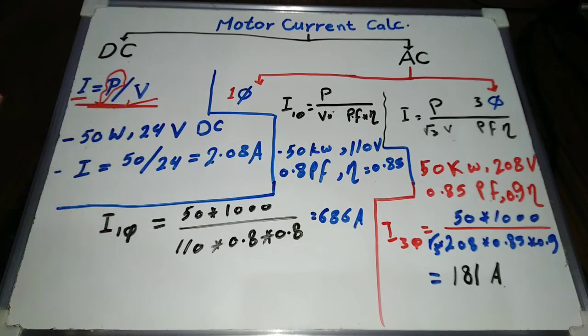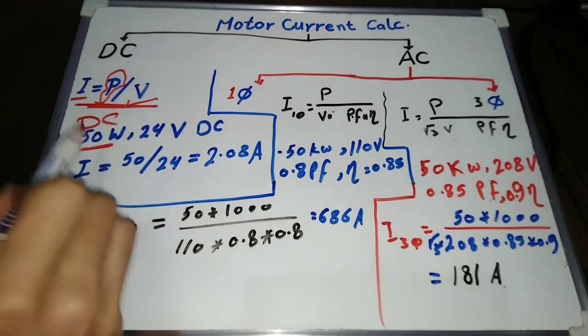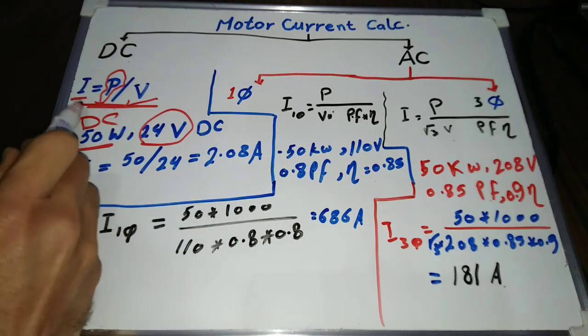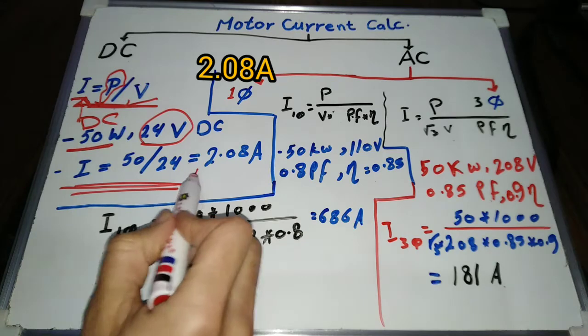Let's have an example. Suppose we have a 50 watt DC motor. Its operating voltage is 24 DC volts. Applying the DC motor current formula, we can calculate the current: I equals 50 divided by 24 equals 2.08 amps.